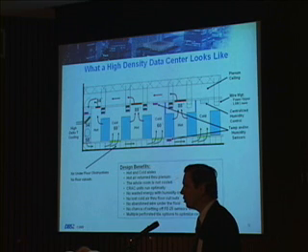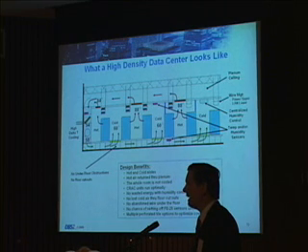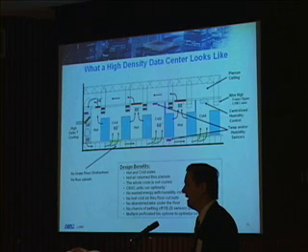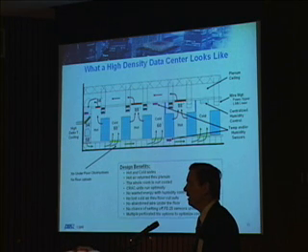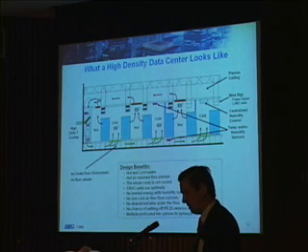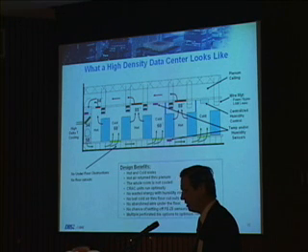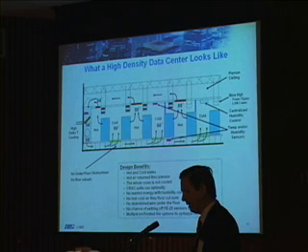We've switched almost all our data centers to this design now. Over time, we've seen a 20% reduction in energy cost. A 20% reduction in energy cost just by going to the plenum ceilings and getting the air out of the data center up into that ceiling area. And there's a lot of other things you can do in that area, and we can talk about that when there's more time.